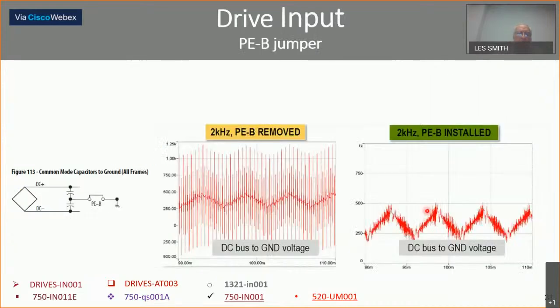Here's the reason for that ground jumper. This is the PEB jumper. If I put the ground jumper in here, look at this. The noise is between 500 and 250. We have 250 volts of noise that will be riding on this bus. Pull this jumper out. Now look, we have the noise going up to over 1,000 volts, and that's on the bus because we're not filtering it out.